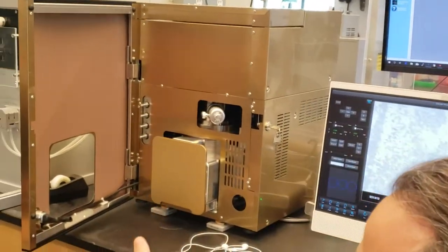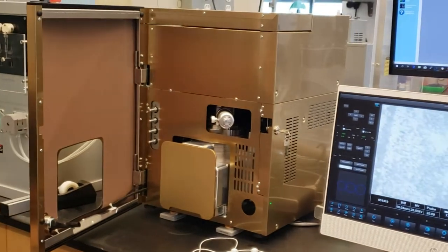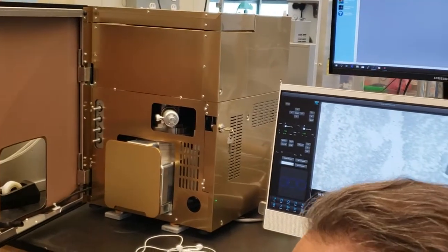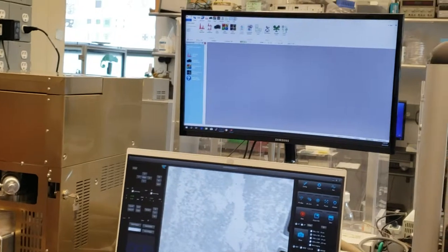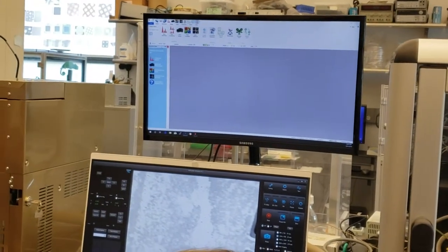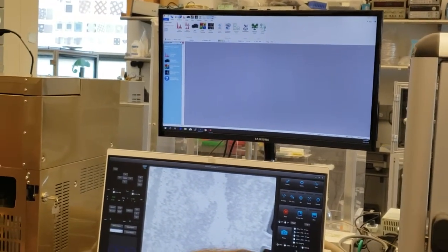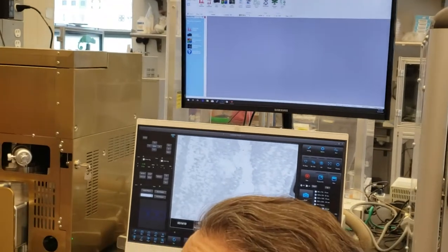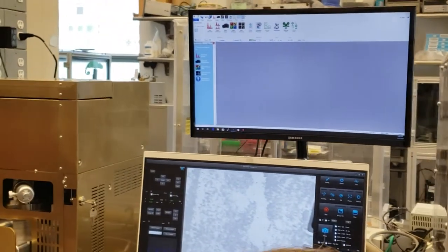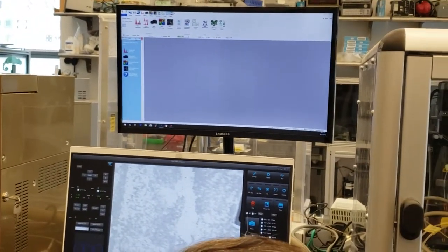So if I was to open up this aperture, right, this is an aperture, if I start dialing that out and get to one of our bigger apertures, I might pull 60, 70, 80,000 counts a second, which would be great if we're doing X-ray maps. If we're trying to focus an image at 10,000x, it might not be too good. But if we're looking at an image at 200x, we could look at an X-ray map at 60,000 counts a second and develop a map in a second.